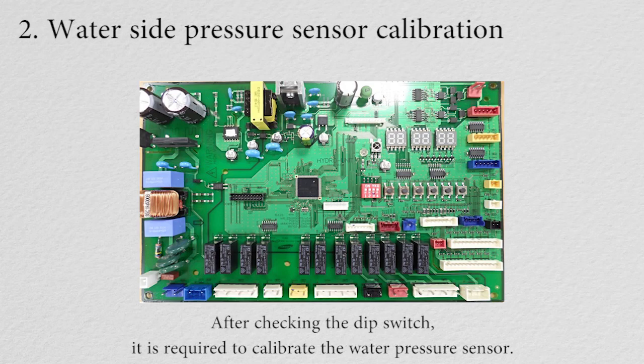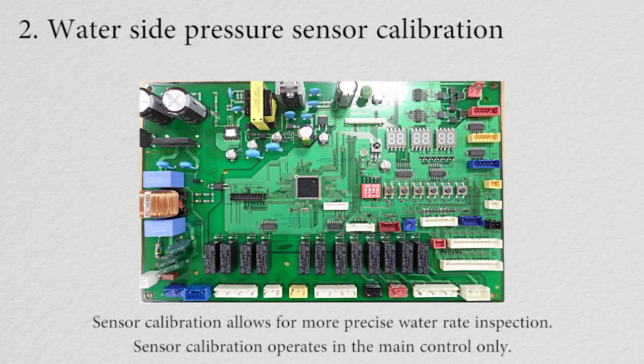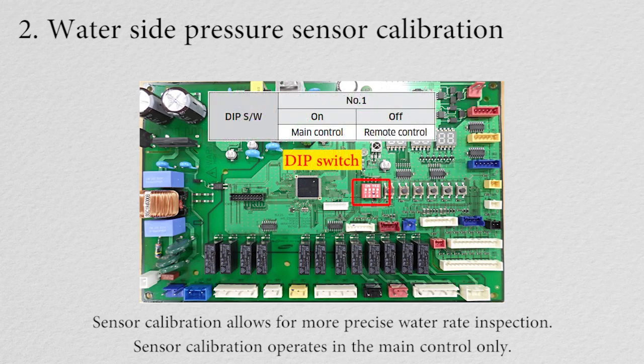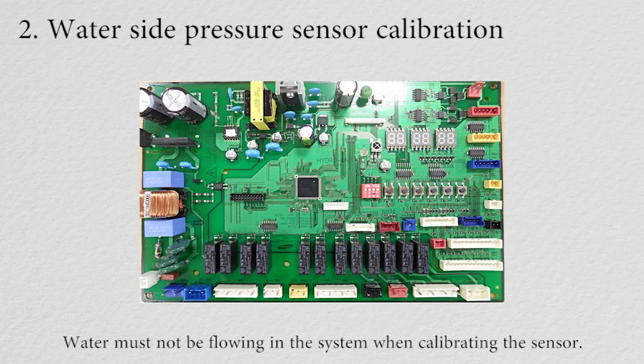After checking the dip switch, it is required to calibrate the water pressure sensor. Sensor calibration allows for more precise water rate inspection. Sensor calibration operates in the main control only. Water must not be flowing in the system when calibrating the sensor.